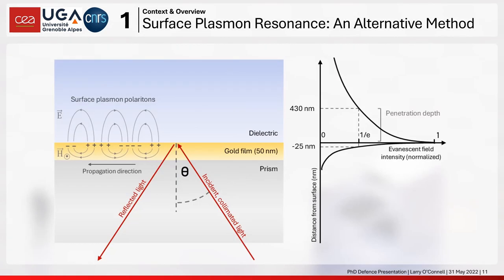The method we explored is called surface plasmon resonance, or SPR. Essentially, we have a glass prism with a thin metal film on top, interfaced with a liquid analyte — in our case, bacteria. When light is incident on this metal-dielectric boundary, at certain angles there is a drop in reflectivity, because light couples to collective oscillations of the conduction electrons in the metal, forming surface plasmon polaritons. The angle at which you see this drop depends heavily on the refractive index of the dielectric just above the sensor surface, within the penetration depth of the evanescent wave.